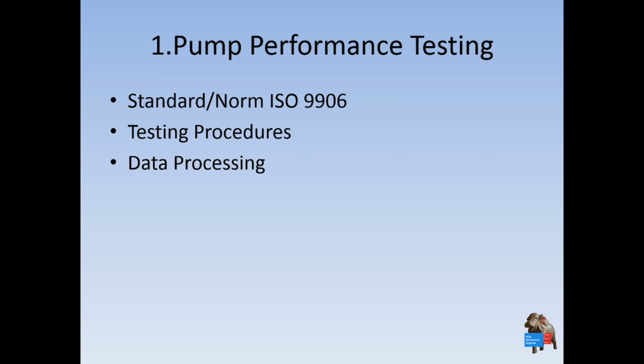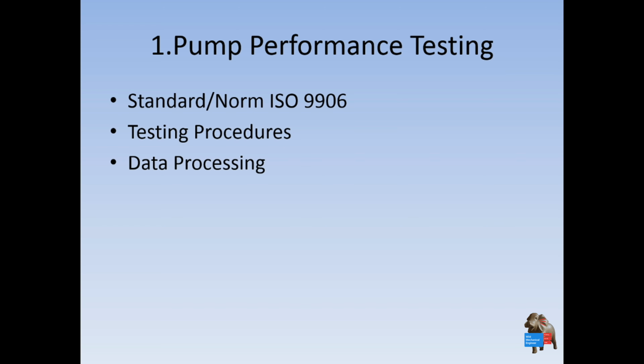On this page, as you can see, pump performance is tested based on the standard or norm ISO 9906. This ISO standard mentions how the pump should be tested, and also guides how the test bed or test rig should be built to meet the standard requirements. In this presentation I will show you how the test is performed, and how the data is processed and then displayed to show the pump performance.